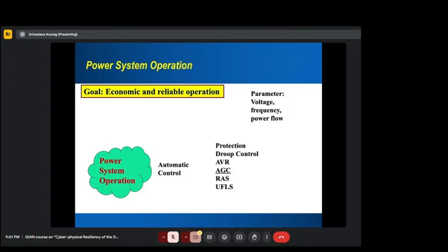Then there's a droop frequency control, which is installed in generation, and it is trying to control the frequency as it sees that real power needs to be changed to fix the frequency. So droop control is basically responding to the frequency increase or decrease by changing the real power.